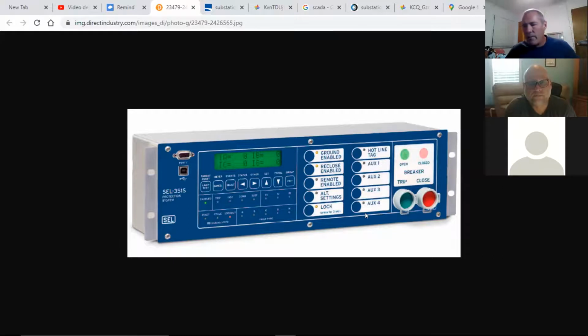But then that night we had a thunderstorm and lost about 6 breakers in the area, and you pretty much had to do everything manually. We didn't do anything more than what we're looking at right here: either trip open or get hotline tags and go from remote to local.